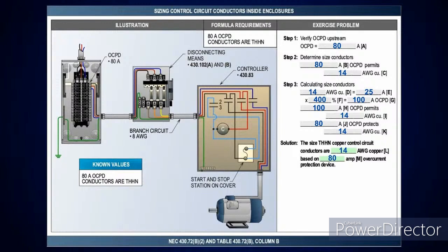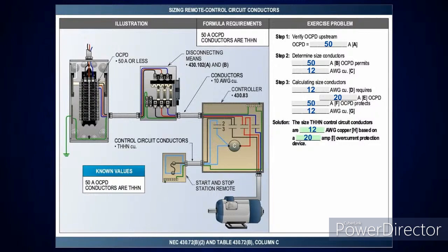And then when I go to a remote type, now you're going in conduit over, so now you're not in free air. So when you look at column C and pick up the notes below it, it's going to tell you you're going to use table 310.16 because you're in a raceway. So it says here a 50 amp will permit what? A number 12. Well, how do I prove that? All I've got to do is look at sizing the conductors, and it's going to tell you that number 12 requires what? A 20 amp overcurrent protection device. So therefore, a 50 amp is permitted to protect that number 12 conductor.